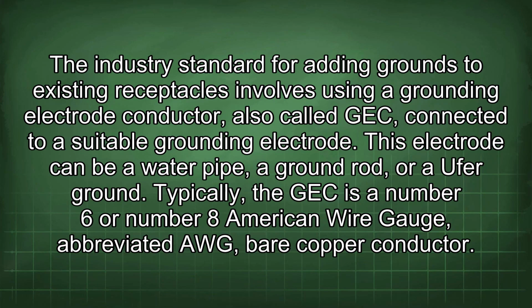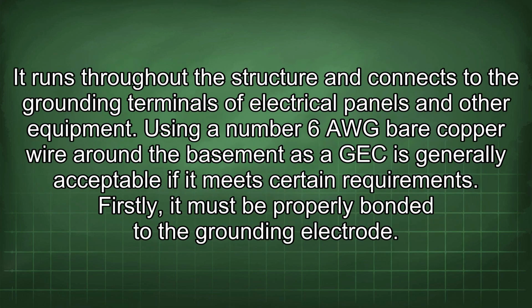The industry standard for adding grounds to existing receptacles involves using a grounding electrode conductor, also called GEC, connected to a suitable grounding electrode. This electrode can be a water pipe, a ground rod, or a Ufer ground. Typically, the GEC is a number 6 or number 8 American wire gauge, abbreviated AWG, bare copper conductor. It runs throughout the structure and connects to the grounding terminals of electrical panels and other equipment.